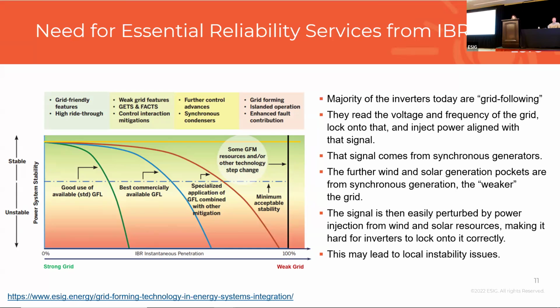Now, if we progress even more, maybe to say 65% of inverter-based resources instantaneously, there was an ask for further control advances, and maybe now you're required to provide frequency response and dynamic voltage support. System operators also started looking for other supporting technologies like synchronous condensers, for example, to support voltage and sometimes also frequency of the grid.